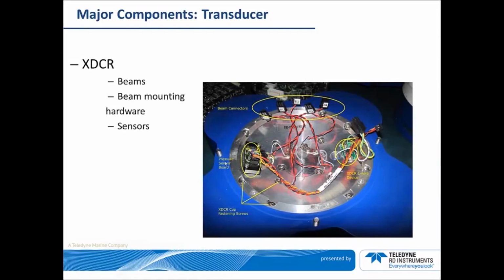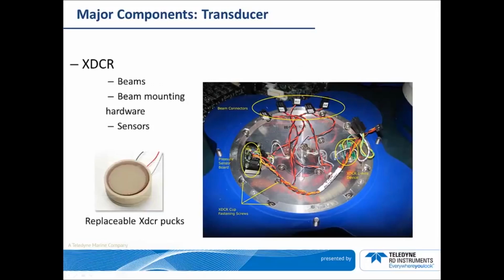Inside the transducer head are the beams, beam mounting hardware, and the sensors. One special characteristic of the Sentinel V from a hardware standpoint is that it has replaceable transducer pucks. This means that if, for any reason, one of the transducer beams is damaged, when you send it back to us for repair, we don't have to replace the entire transducer head, like how it is for the workhorse. Before I proceed, I would just like to note again that more often than not, there shouldn't be any reason why a Sentinel V user would be accessing these components. This is just strictly for your information.